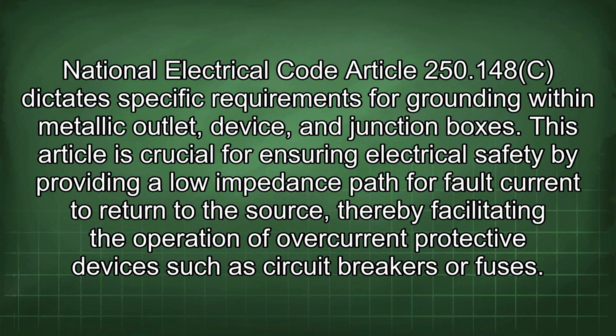National Electrical Code Article 250.148C dictates specific requirements for grounding within metallic outlet, device, and junction boxes. This article is crucial for ensuring electrical safety by providing a low impedance path for fault current to return to the source, thereby facilitating the operation of overcurrent protective devices such as circuit breakers or fuses.